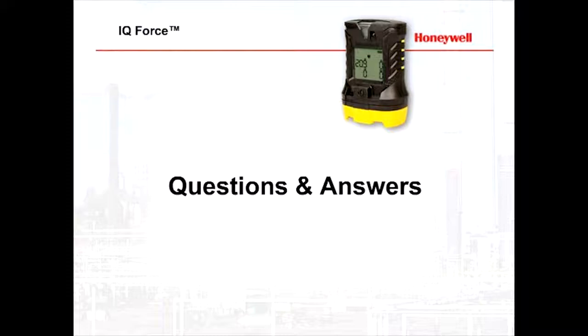All right. Can the IQ Force be configured for operation without putting it in a dock or connecting it to a computer? Yeah, absolutely. It functions like a standard gas detector, so you don't need the dock to use the instrument. We do encourage people to use docks. We believe that they greatly simplify the bump test and calibration processes, as well as they provide you with all the compliance information that you need. And the docks obviously can run in 3 different modes. So the docks can run in standalone mode, or you can connect them on the Ethernet, or you can connect them directly to a computer with the USB cables.